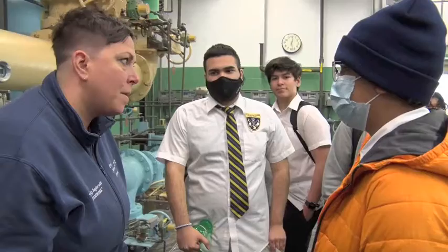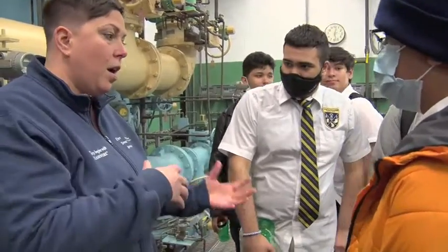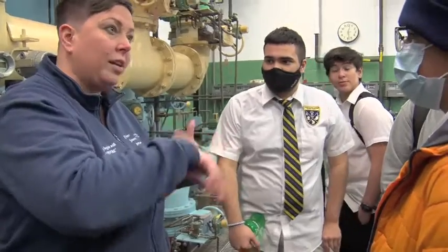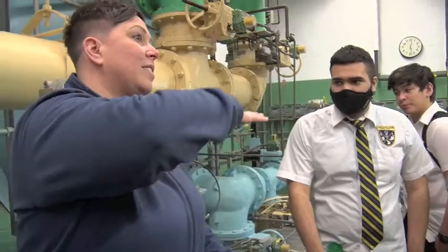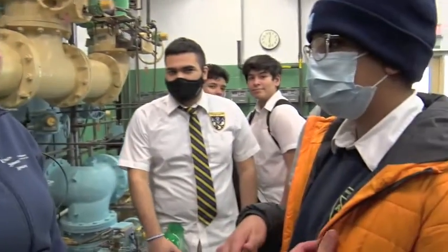Oh, so since iron has a high density, it goes all the way to the bottom. Remember when you were in that chemical building and you saw the coagulant? That mixed with the process of rapid mixing in the mixing chamber, it's called flocculation, makes a floc. It pulls the particles together and then it settles. Then the clean water rises to the top, and that's what goes into the filters. Then we have clean water, ready to be filtered. Understand? Yep. That's a good question.